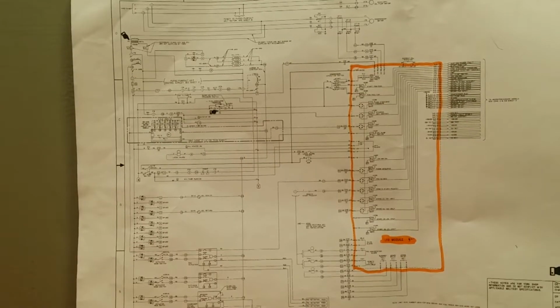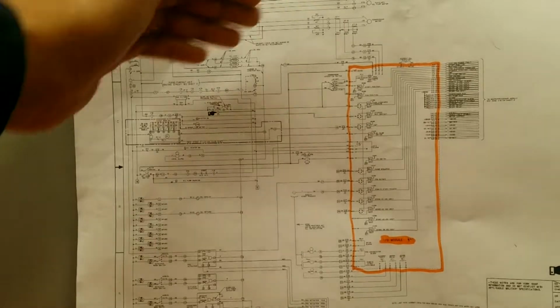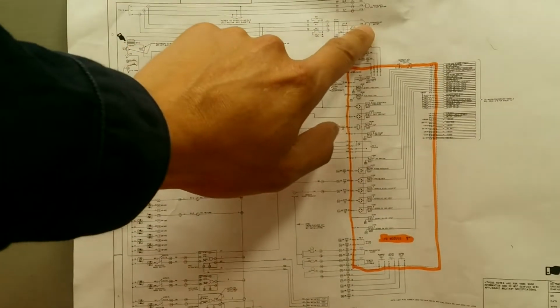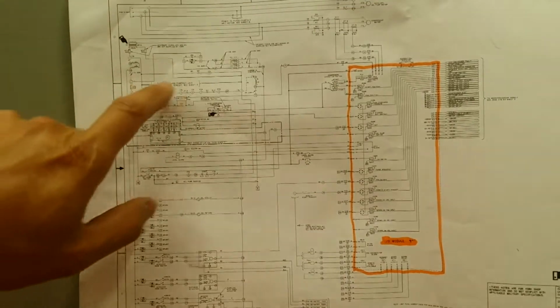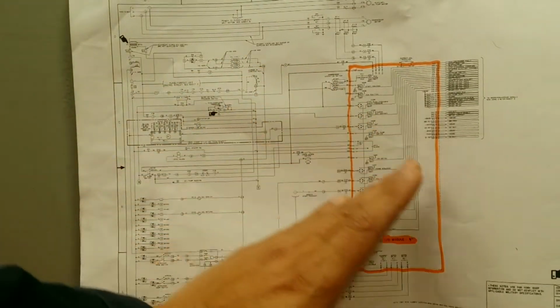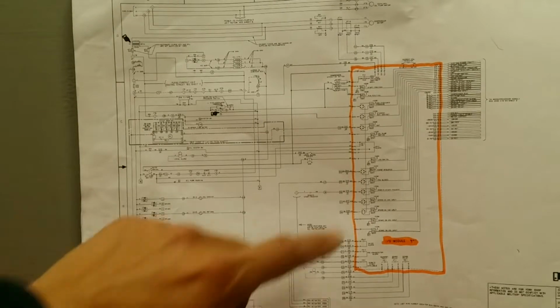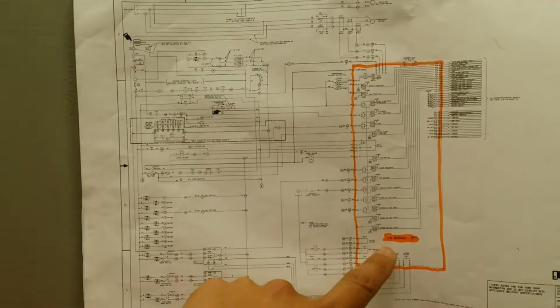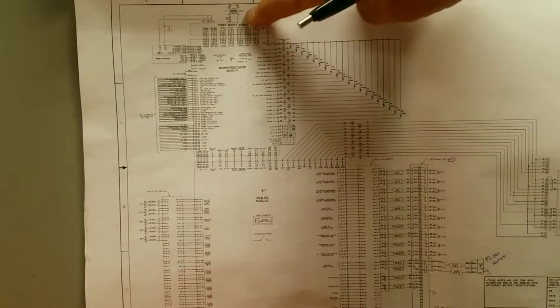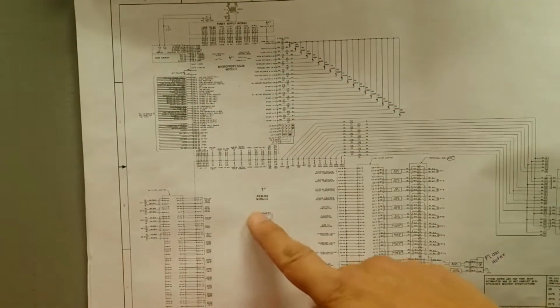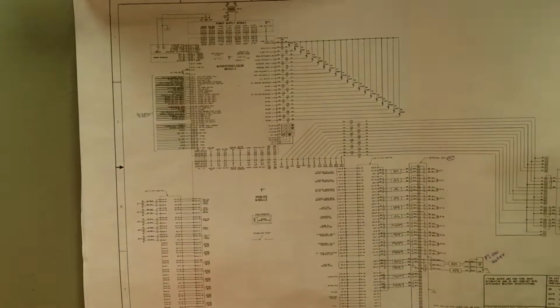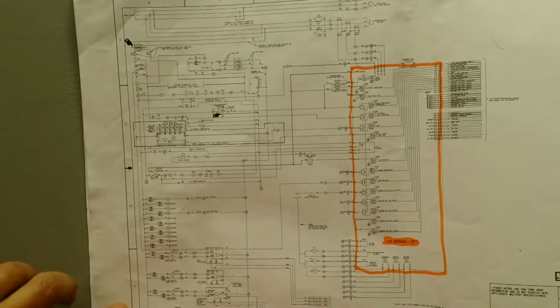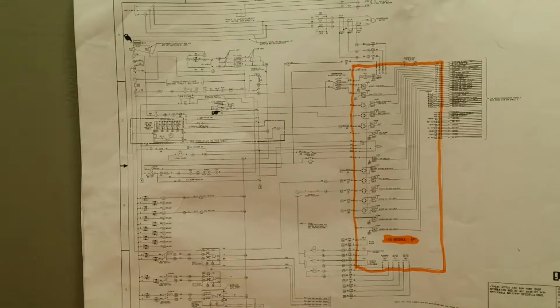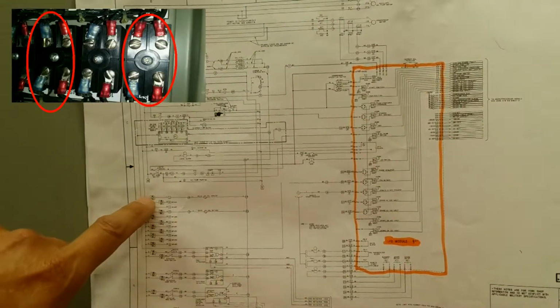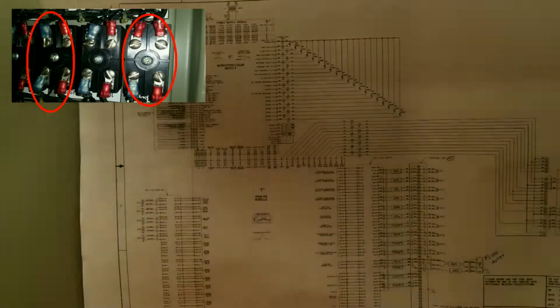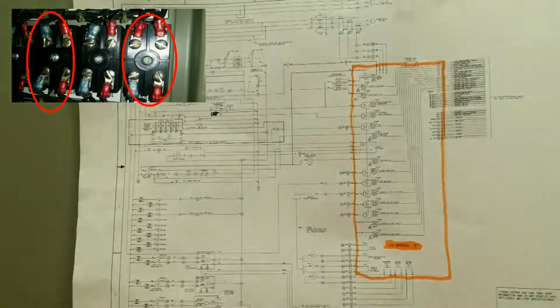So here is the main schematic, and it is divided into a motor controller side, which controls the compressor and the auxiliary oil pump, and the electronic side, which includes all the sensors and the 4 electronic modules. That is the input and output module, the power module, the microprocessor, and finally the analog module. I will talk about all of them, but before that, I'll talk about some of the sensors. The first component that I would like to discuss is the SSR. Here is one side of the SSR, and here is the command of the SSR.